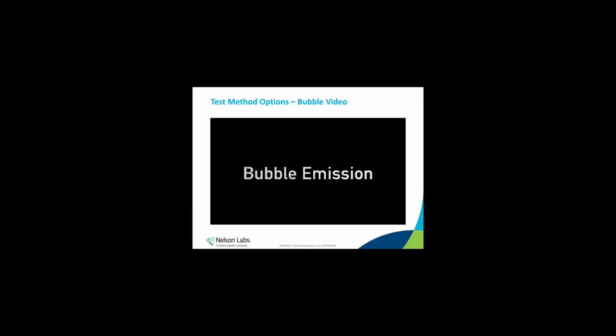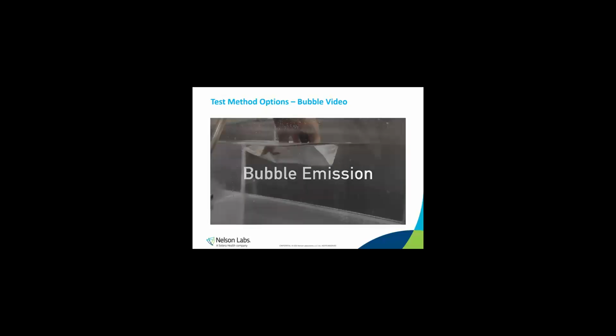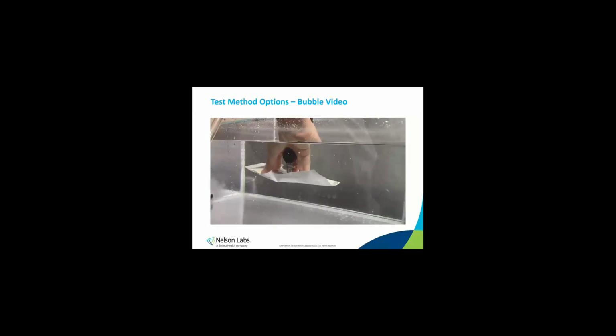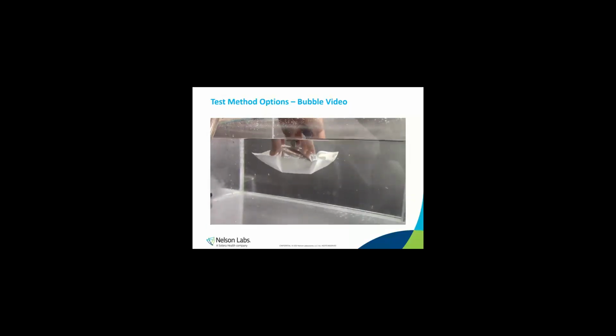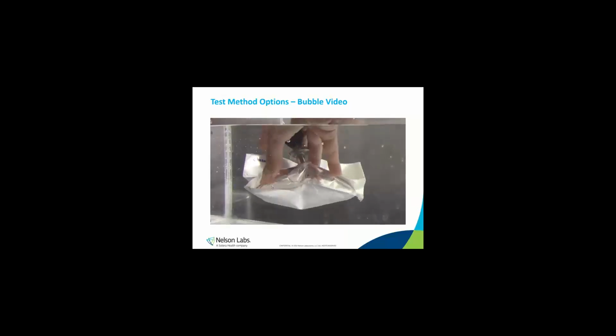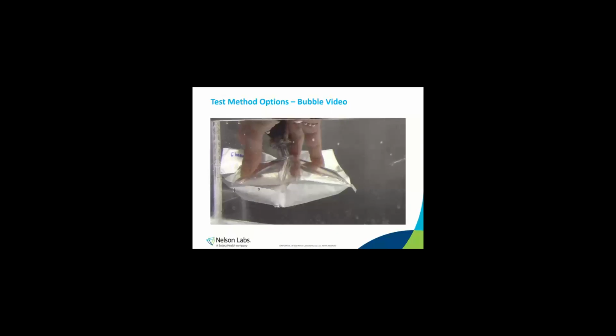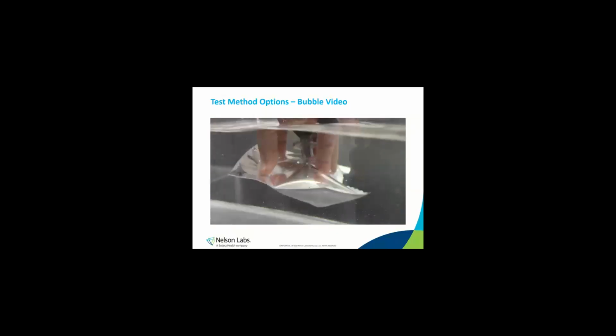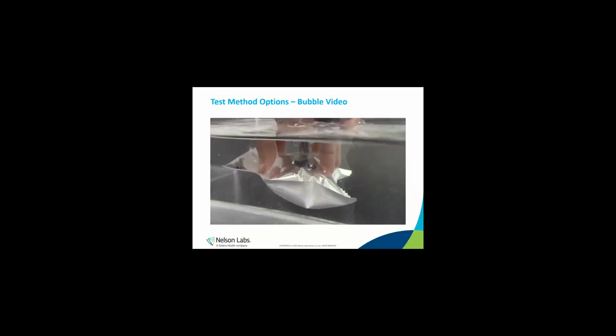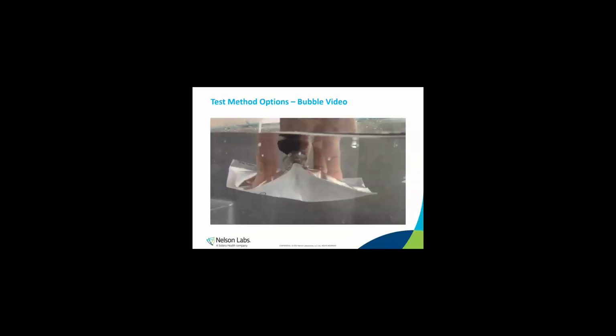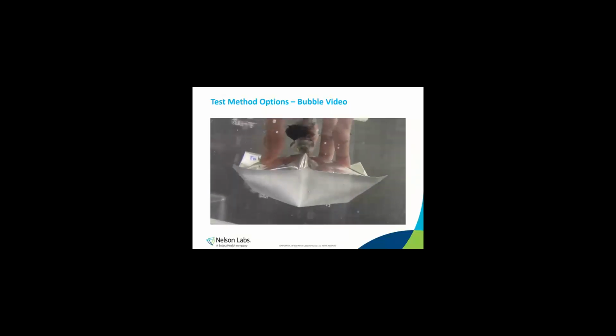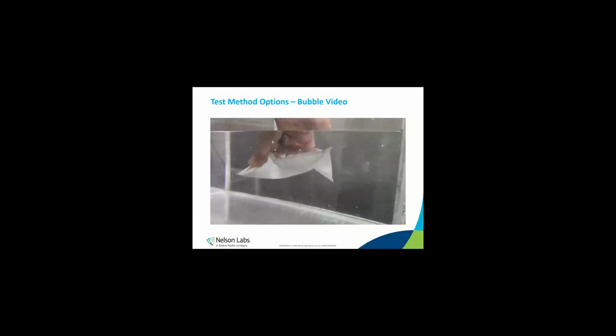And here we can see some examples of what a 250 micron defect would look like. We'll put it in the tub, we'll inflate it to that pressure, and we'll look for bubbles. Now here is a channel leak, and this is a leak. This is a puncture leak here in the film. And now we have one down in the Tyvek.